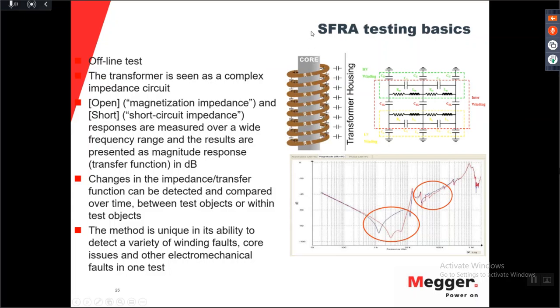And when I inject a signal at the top and I measure it at the bottom, my signal will attenuate. So my signal, how much it is attenuating at different frequencies. Now, if I get a short circuit between this turn and this turn, this capacitance, of course, will be 0. So then my complex circuit has changed, and I will see a difference in my measured curve.